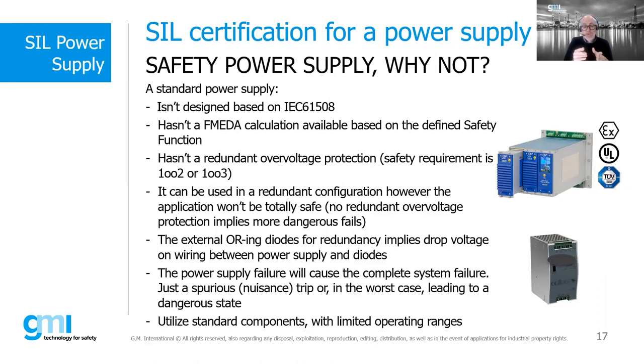And also, standard power supplies often require external OR-ing diodes to allow for redundancy. This means adding external wiring which, especially for high load currents, creates a high voltage drop, which has a strong impact on the supply voltage. It's true that it's possible to adjust the output voltage to compensate for the voltage drop, but this operation increases consumption considerably. In addition, a standard power supply has a higher number of spurious faults than the safety power supply. We know well how a spurious fault can also lead to dangerous failures for the application.